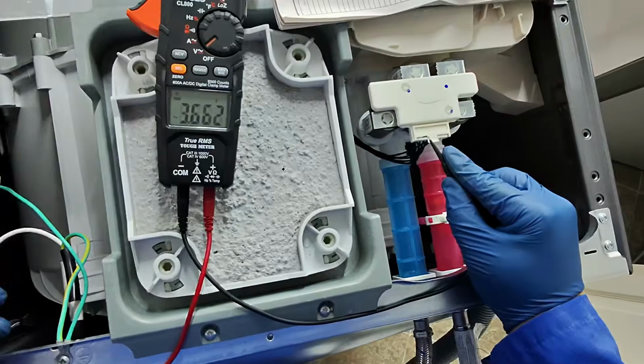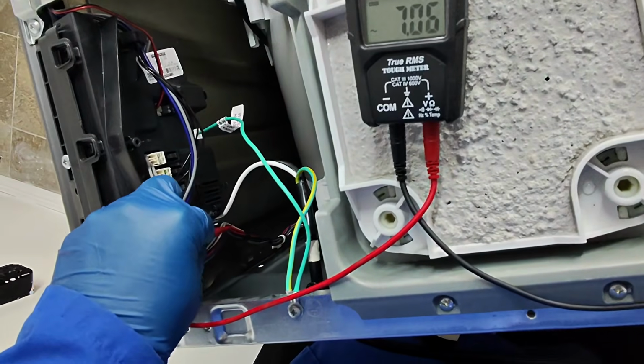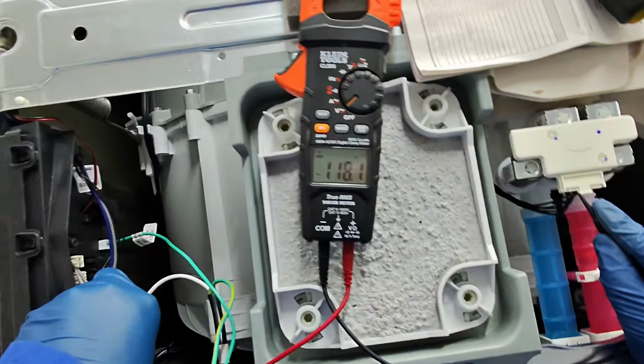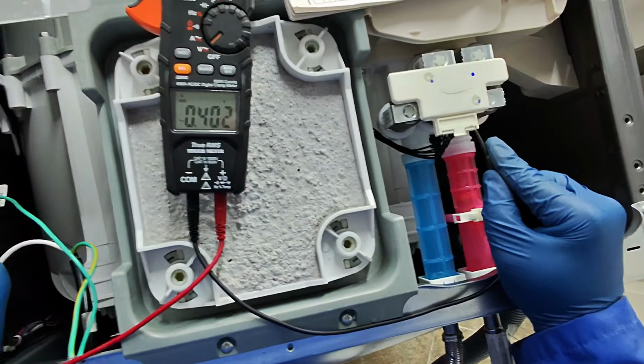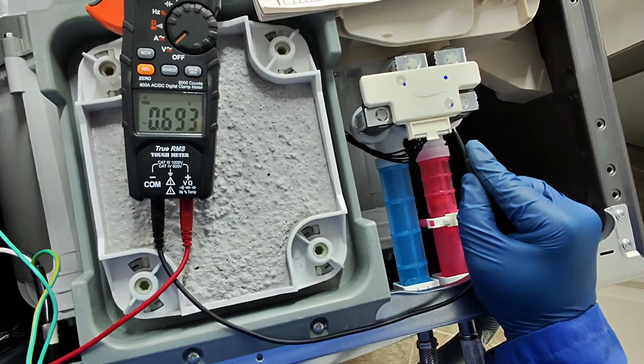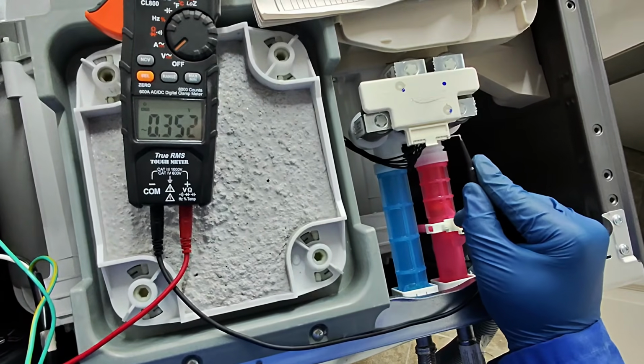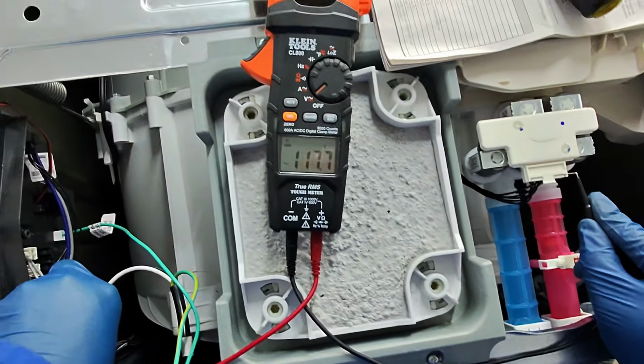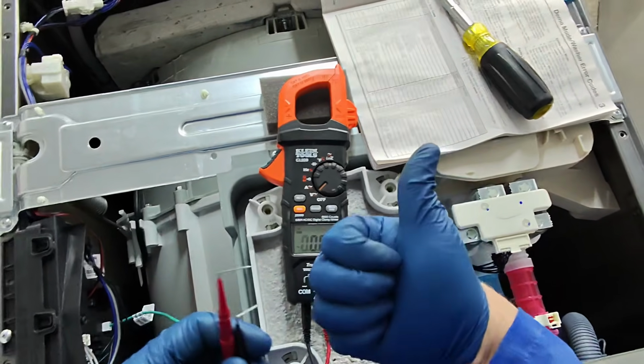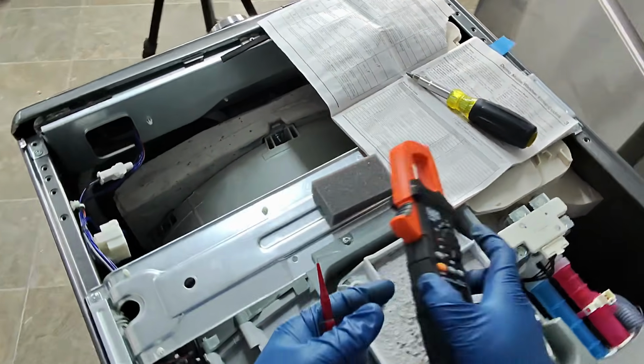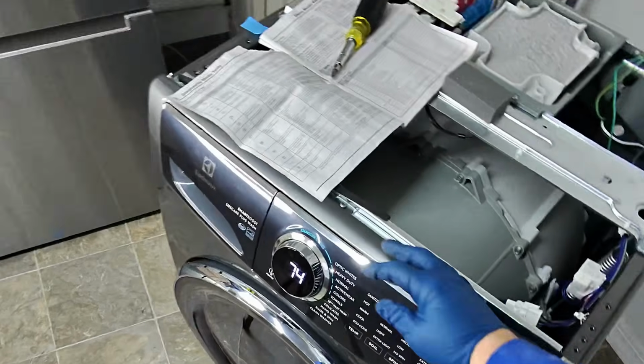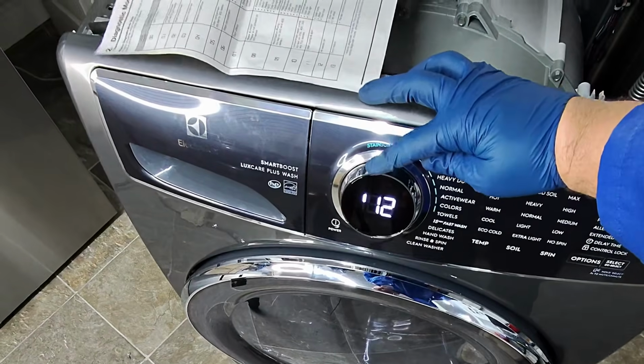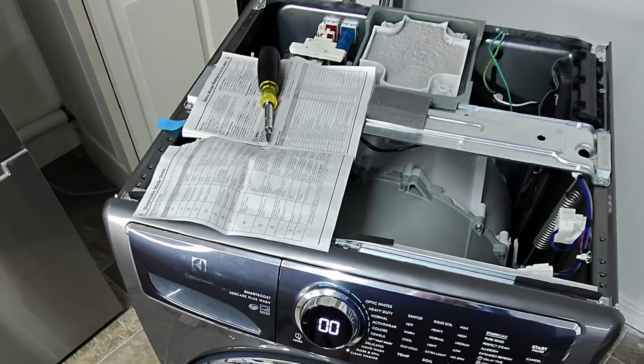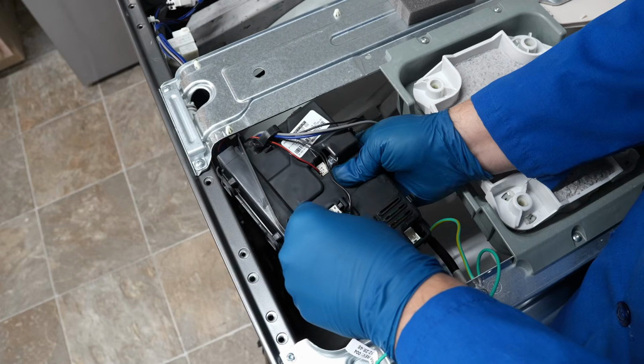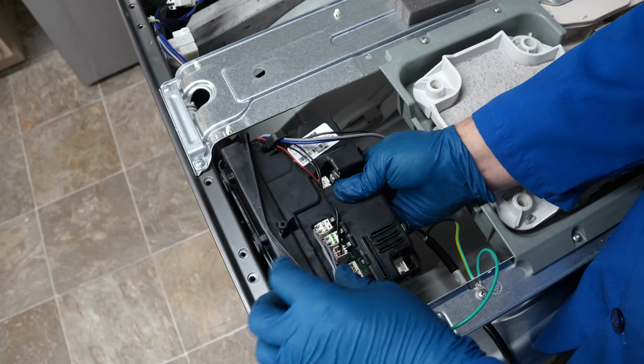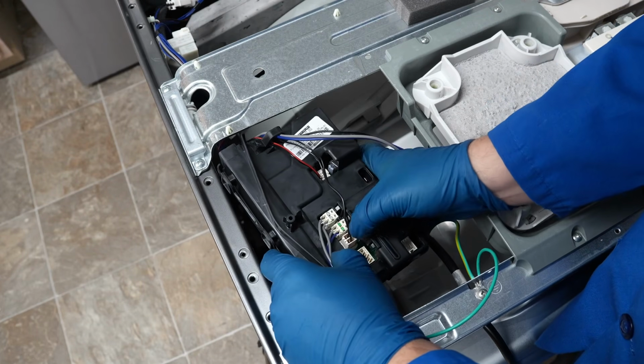Use the other probe of your multimeter and tap it onto the wire harness set that goes to the valves like you see here. Going from J1-2 to any of the top exposed area of the valve harness should get you 120 volts AC. You may need to rotate the dial through number 1 through 6 as it will change which segments of the valve are triggered, but it will allow you to force voltage through to try to see if the valves get 120 volts AC at all. If you don't get 120 volts on any of these areas in the various settings, the board is cooked and it needs replaced.